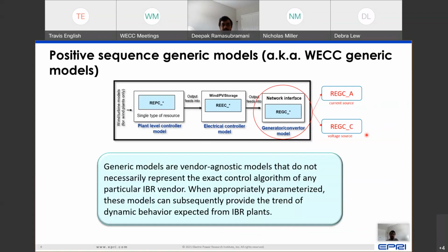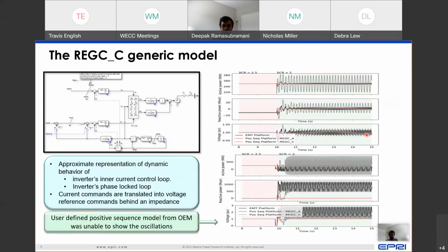Now, this REGC_C model is a much more robust model, especially for low short circuit regions. And we've shown that it can really provide a representation of oscillatory behavior that manifests in low short circuit environments. So here's an example study. The REGC model itself has representation of phase lock loops and inner current control loops and all the good things that are there inside an inverter.